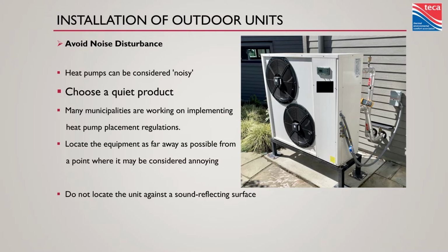So this is a monoblock heat pump, air source, sitting outside somebody's very nice house, up elevated above the snow line. There's some insulated and cladded water piping going into the mechanical room. Cladding helps keep the birds out of it. You want to avoid noise disturbance, so don't put this thing right outside the primary bedroom. Maybe put it somewhere that no one's going to really notice. They are not silent. They're getting better, but they're not silent. Choose a quiet product. If you're trying to keep it quiet, start quiet. Thing about noise is it doesn't get any quieter than at the source.